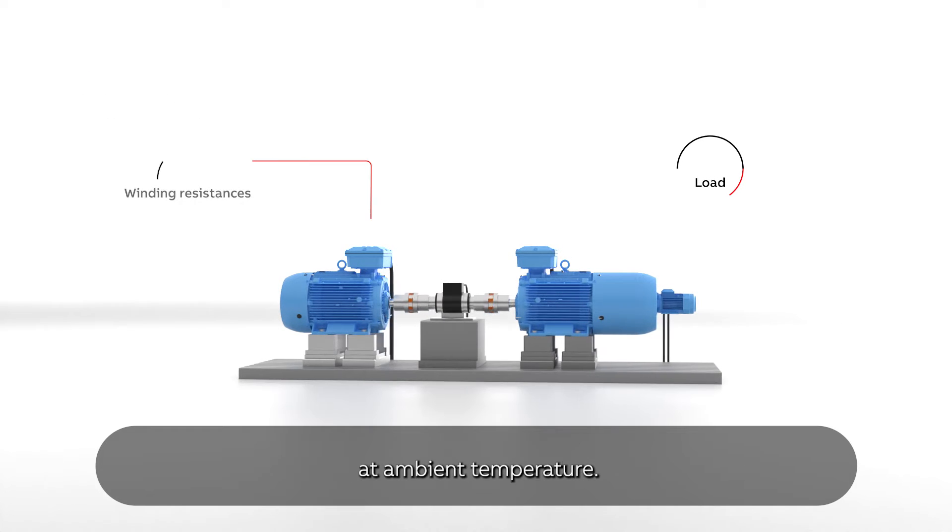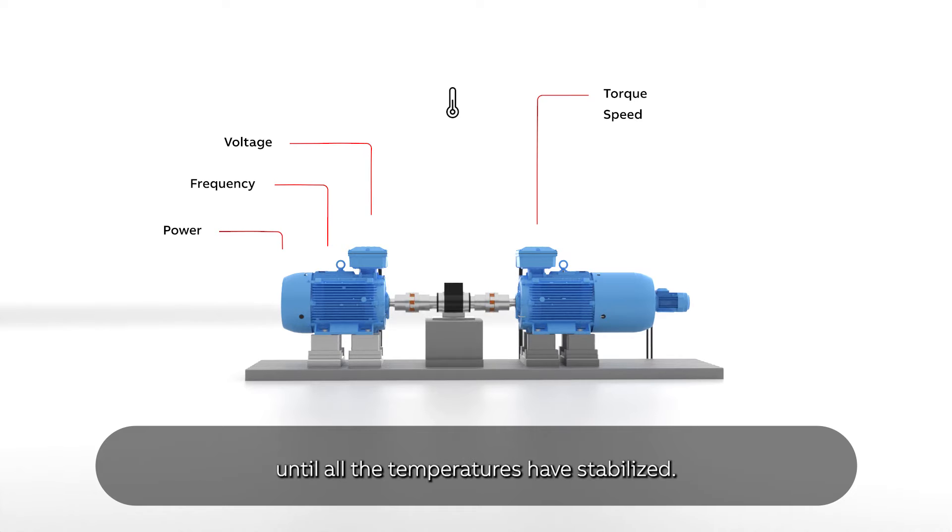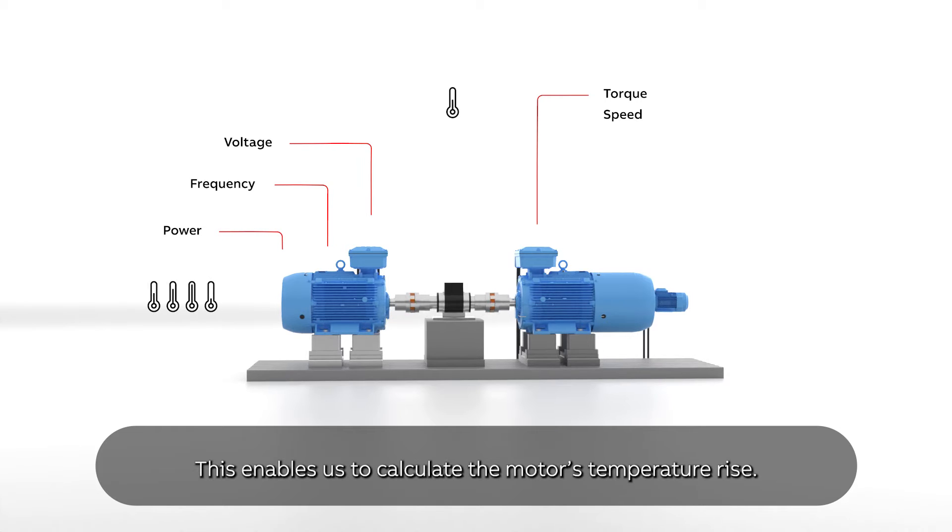First we measure the resistances of the stator winding at ambient temperature. Then we run the motor at its rated voltage, frequency and power until all the temperatures have stabilized. This enables us to calculate the motor's temperature rise.